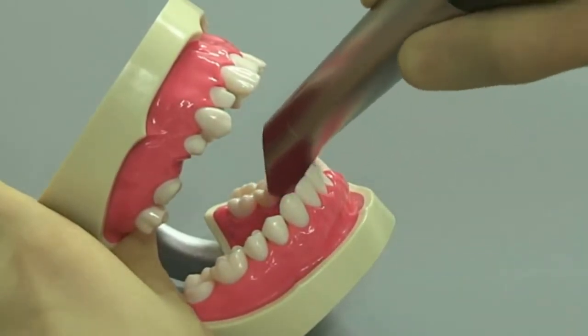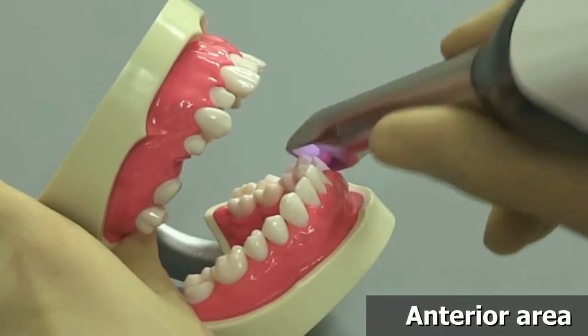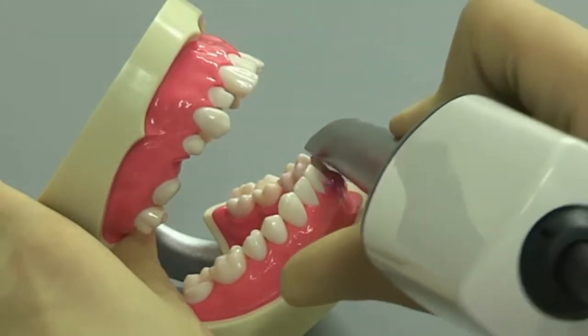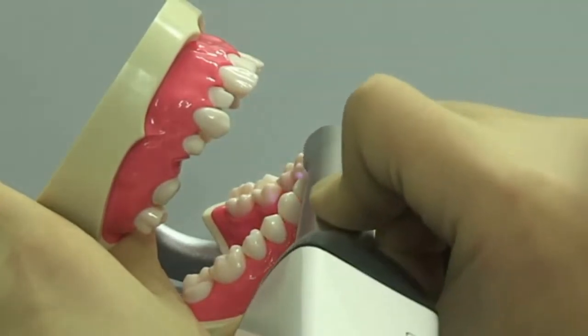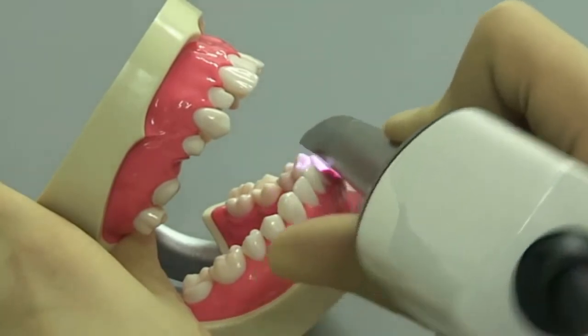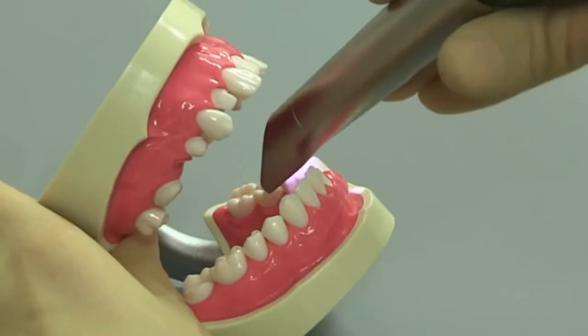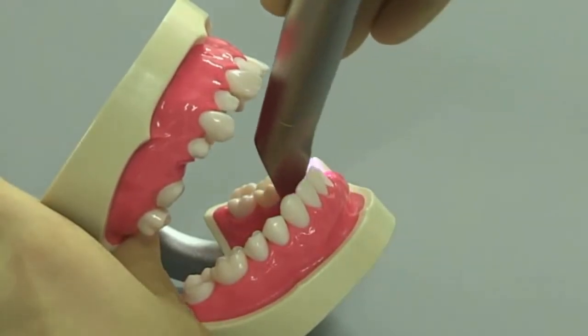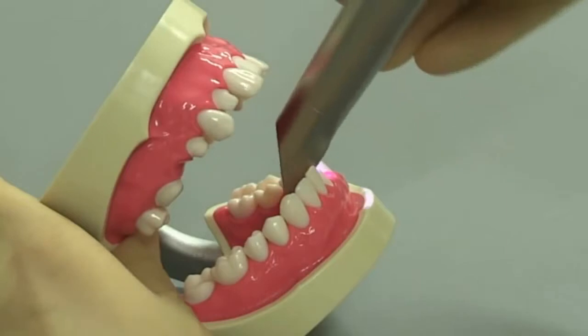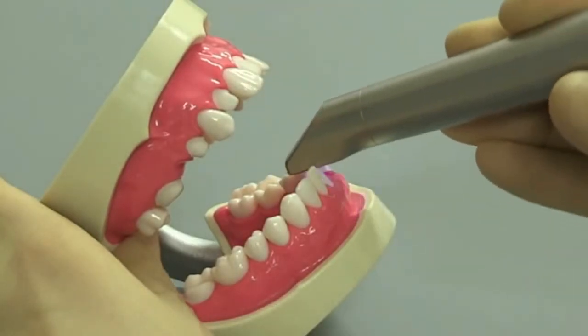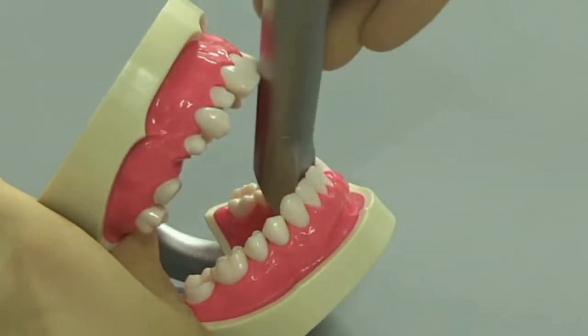Begin scanning the anterior area by starting with the premolar. Guide the camera in mesial direction labially over the anterior teeth up to the first position of the neighboring quadrant and from there back to the premolar.